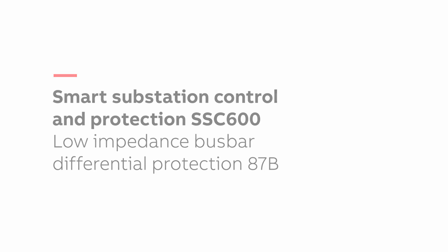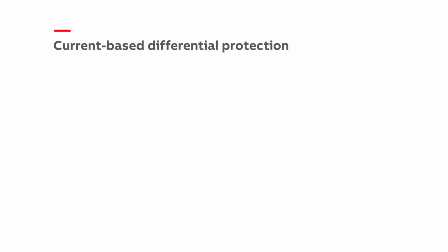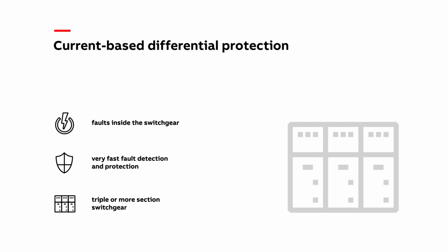What is busbar differential protection? Low impedance-based busbar differential protection, also known as 87B, is current-based differential protection, which is very important for clearing faults inside the switchgear and mitigating impact. The response time is very fast. It is one of the fastest protection functions, and it can be used for switchgear with multiple sections.